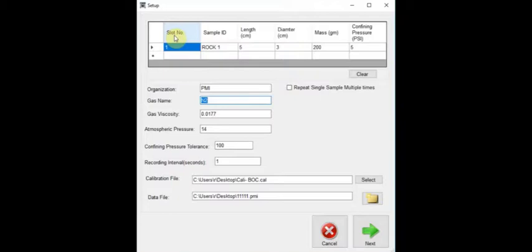Below this table we can input an organization, the type of gas being used, and the gas's viscosity. We also need to input atmospheric pressure along with the confining pressure tolerance and the desired recording interval. Next, we will see a field to browse to a calibration file. This file is generated when we run a calibration. Under this is the file path to save the data file that will be produced from the auto test. Then we can see an option to cancel or proceed with starting the auto test.